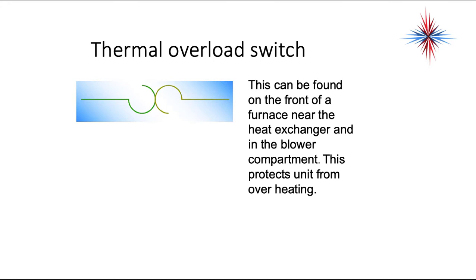This is a thermal overload. It can be found on the front of a furnace near the heat exchanger in the blower compartment. This protects a unit from overheating. It's also found internally in some motors to prevent the motor from overheating. If the temperature rises, the two elements will pull apart and open the circuit.